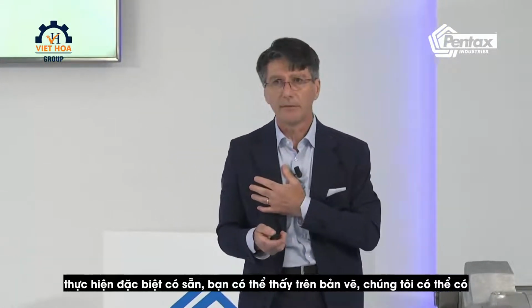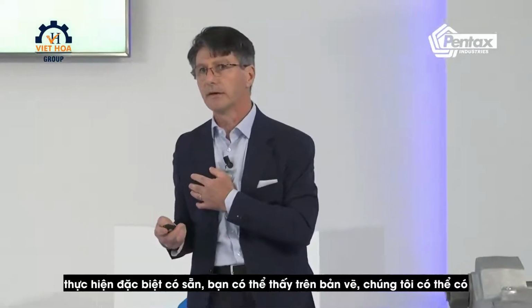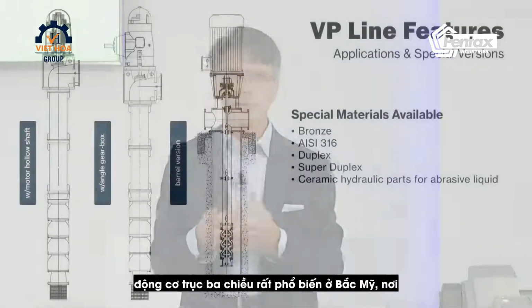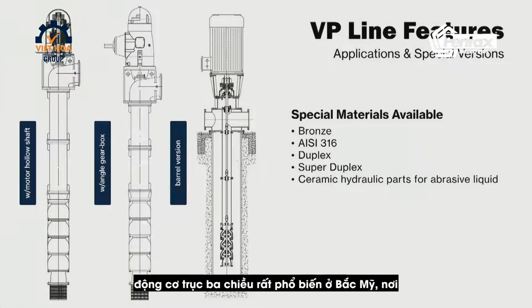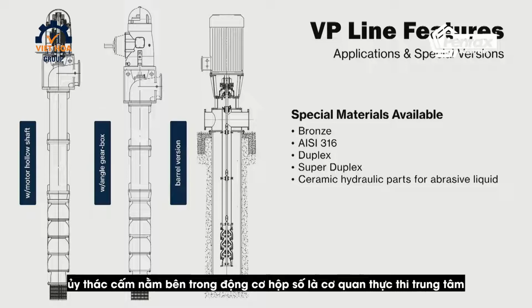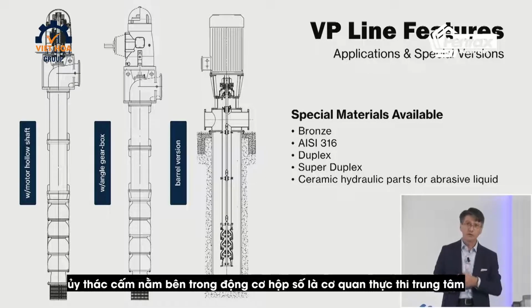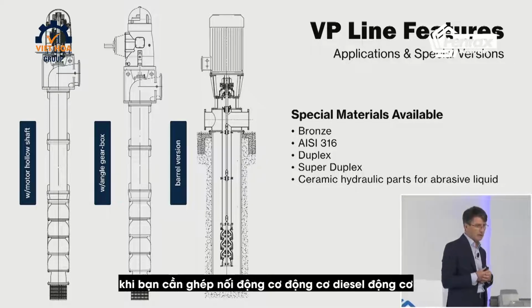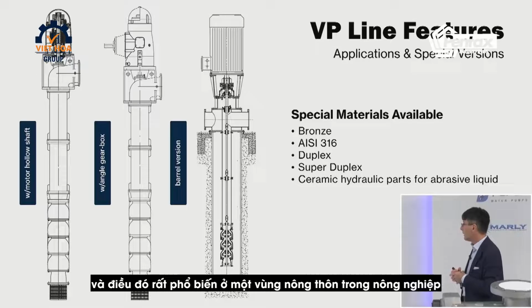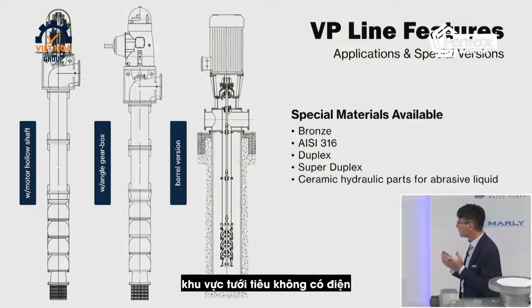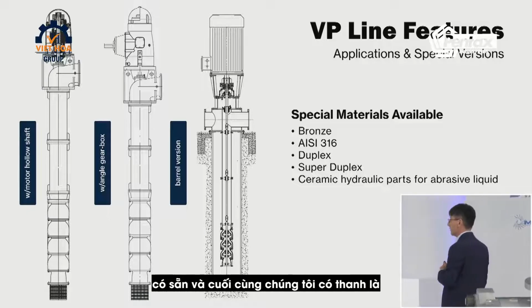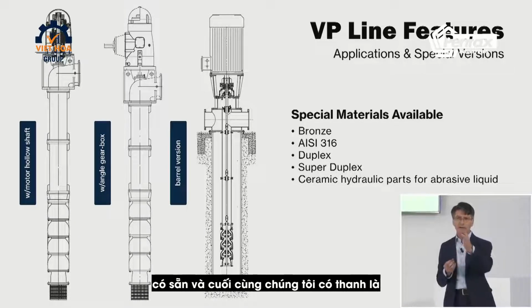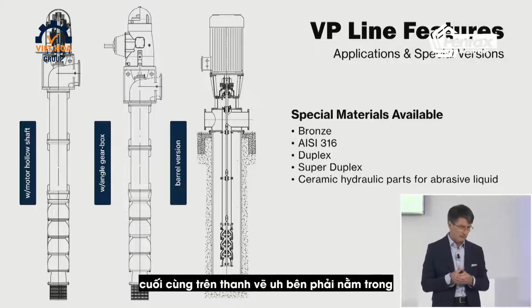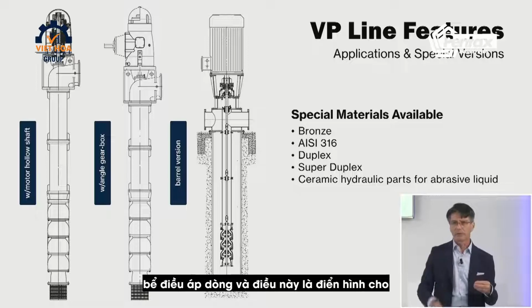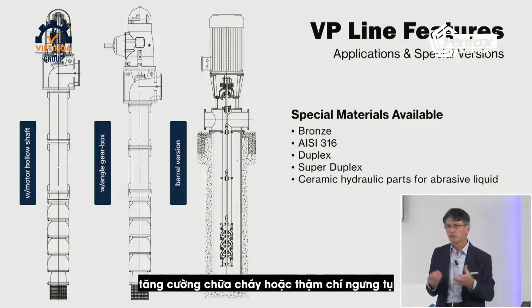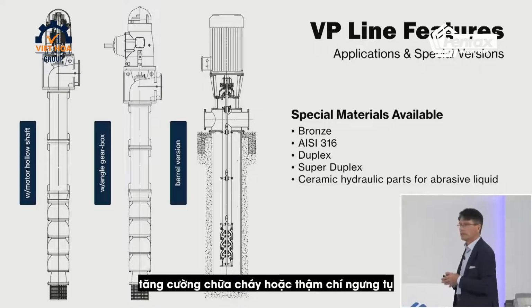Special executions available. You can see on the drawing, we can have hollow shaft motor, very common in North America, where the thrust bearing is located inside the motor. The gearbox is the execution when you need to couple the diesel engine motor, and that is very common in rural areas, in the agricultural irrigation area where the electricity is not available. And finally, we have the barrel, the last on the right-hand drawing. Barrel is an inline, pressurized tank, and this is typical for boosting, firefighting, or even condensate.